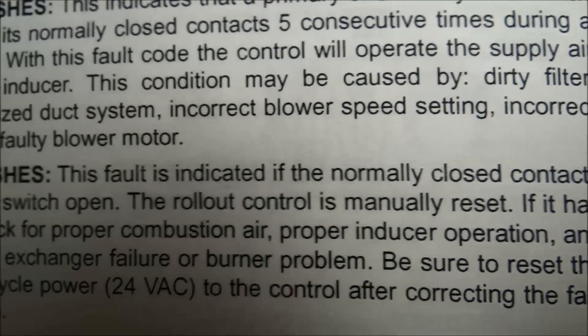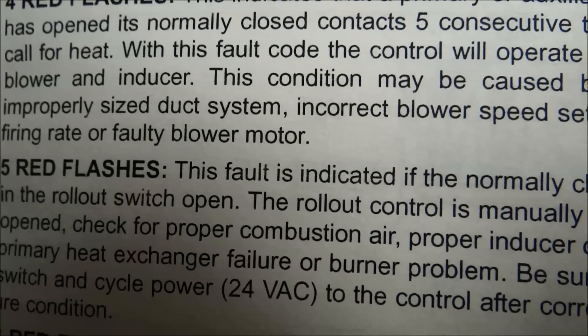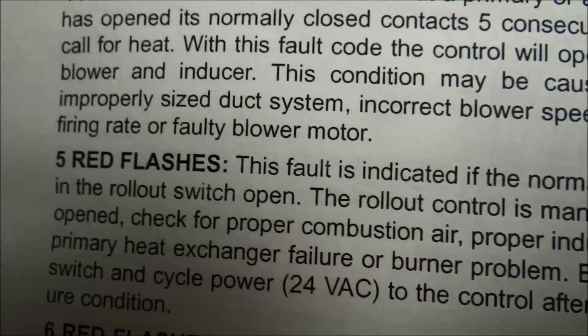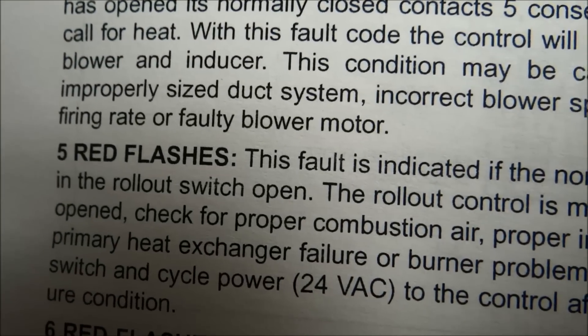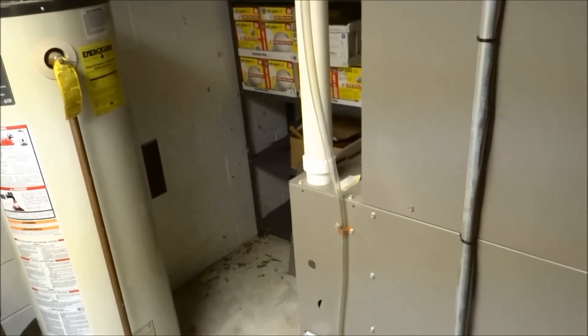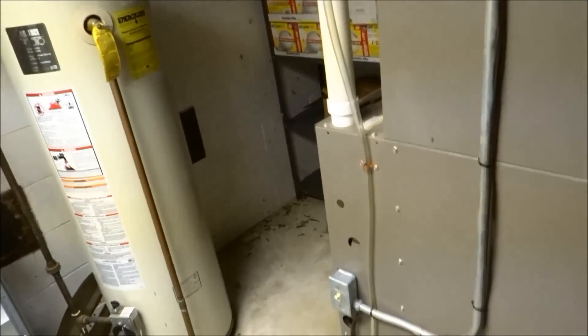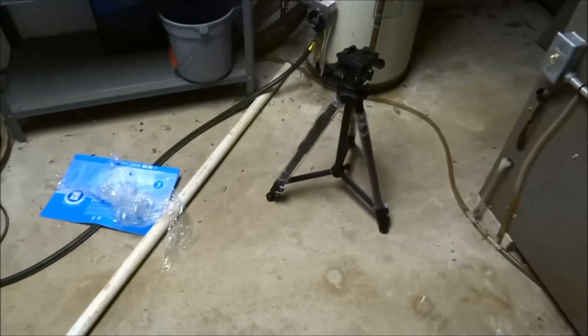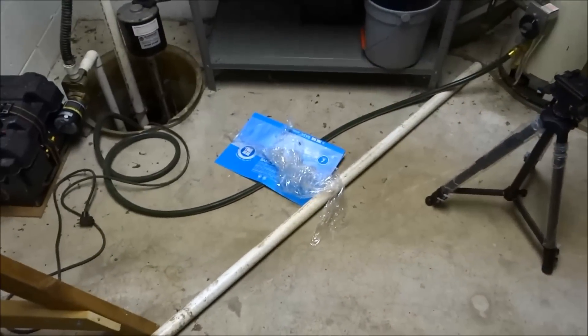The condition may be caused by dirty filter, improperly sized duct system, incorrect blower speed setting, incorrect firing rate, or faulty blower motor. I'm pretty sure my ductwork hasn't changed. This furnace has been working for nine, almost ten years, and I just replaced the filters. That's the old filter — the filter is brand new. So let's take a look at the schematic.